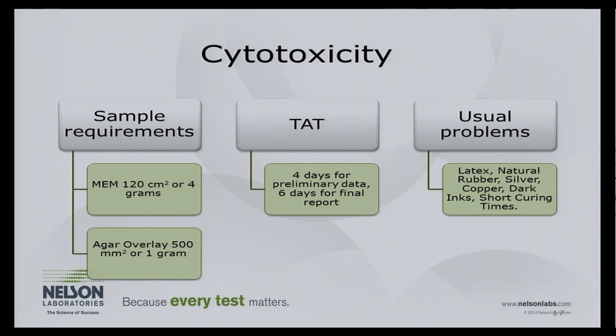Common problem materials in cytotox: latex is our positive control, so if your device contains latex it will fail. Natural rubber is the same. Silver, copper, and zinc metals will all fail cytotoxicity. Short curing times on inks and adhesives also cause failures — many inks contain silver and copper. We use what we jokingly call the 'smell test' at Nelson Labs: if you open a device from its bag and smell a volatile chemical, those chemicals will go into the extract and likely cause a failure, indicating the device hasn't been fully cured.